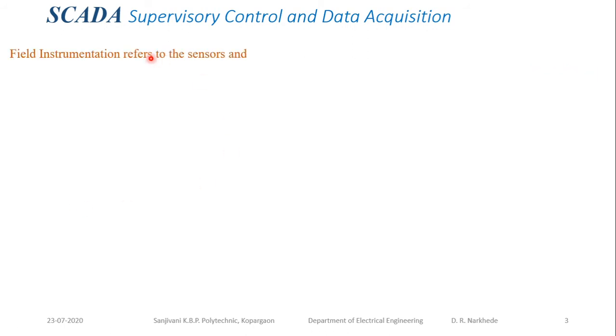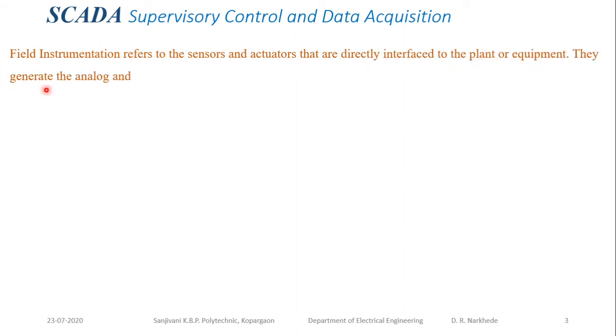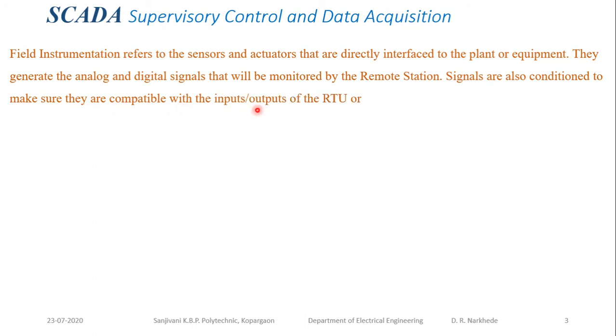Field instrumentation refers to the sensors and actuators that are directly interfaced to the plant or equipment. They generate analog and digital signals that are monitored by the remote station. Signals are also conditioned to make sure they are compatible with the inputs and outputs of the RTU — Remote Terminal Unit — or PLC at the remote station. The sensors are input devices and actuators are output devices, directly connected to the plant or equipment.